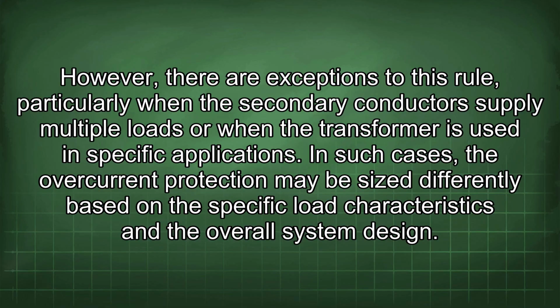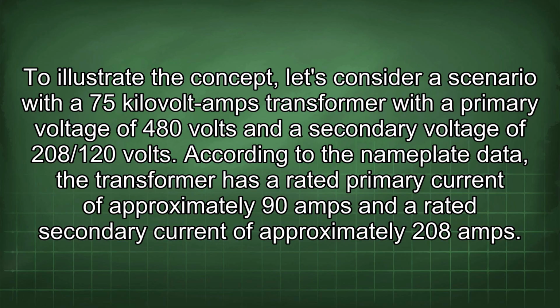In such cases, the overcurrent protection may be sized differently based on the specific load characteristics and the overall system design. To illustrate the concept, let's consider a scenario with a 75 kVA transformer with a primary voltage of 480 volts and a secondary voltage of 208/120 volts. According to the nameplate data, the transformer has a rated primary current of approximately 90 amps and a rated secondary current of approximately 208 amps.